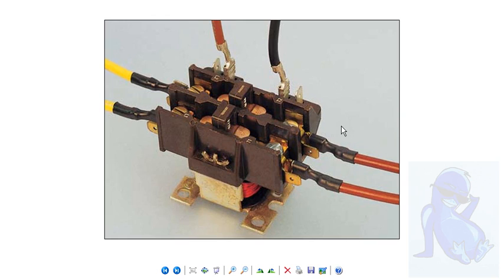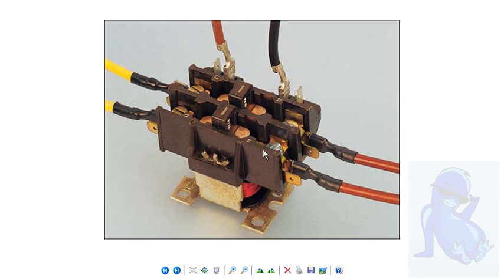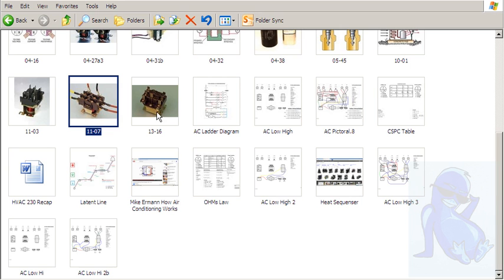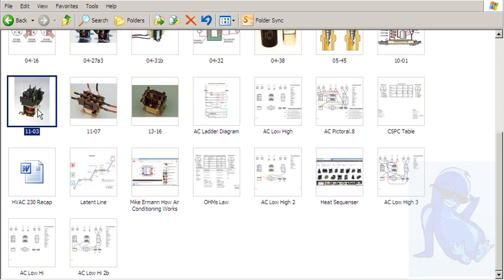Corrosion. That's one of the biggest faults out there that you're going to find. And then these things do go bad. The coils overheat. Ants get in there and they tend to fry them out too. It's a little cheap part. You can get it from Grainger. Buy it online. Go to a supply house and change it out.